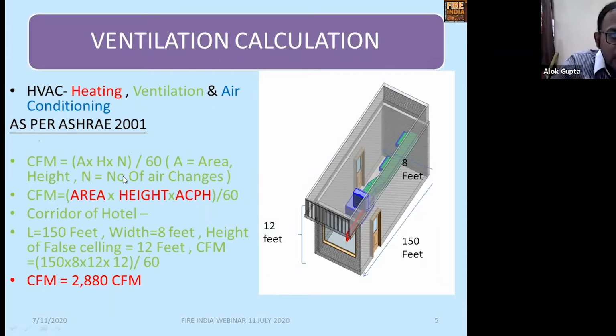This is A times H times N, where N is the number of air changes. We always hear like 8 air changes, 12 air changes. So it's area times height times number of air changes, divided by 60. In this case, length is 150 feet, width is 8 feet, and height is approximately 12 feet. This calculation gives us a requirement of an exhaust fan of 2880 CFM.